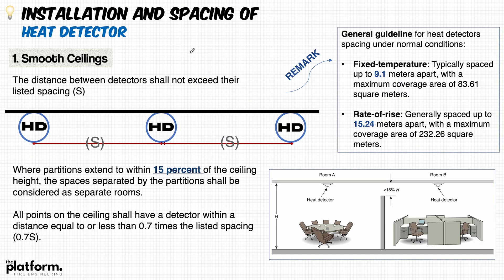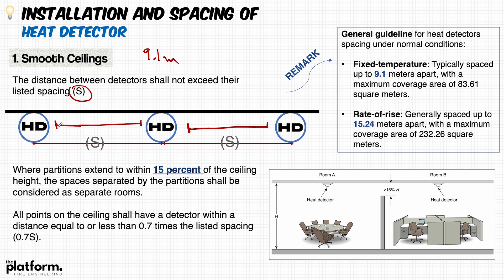Similar to smoke detectors, different ceiling types affect the spacing distances for heat detectors. The listed spacing for heat detectors — referring to a smooth ceiling as explained in lectures 4 and 5 for smoke detectors — is 9.1 meters between each heat detector.